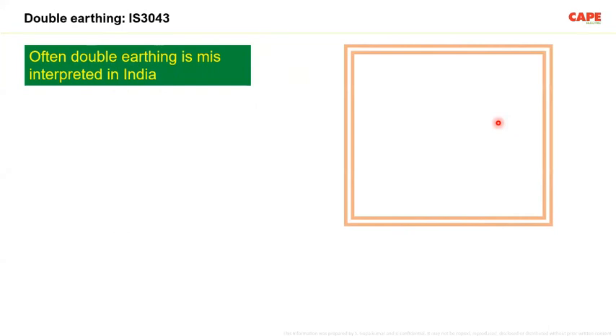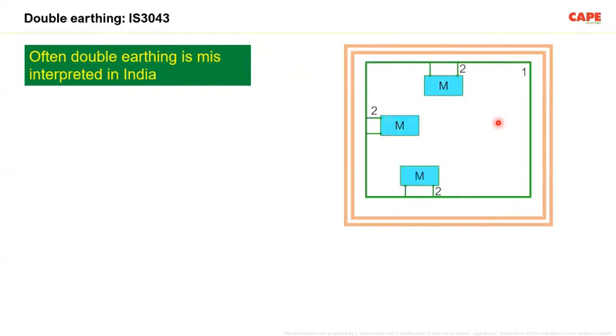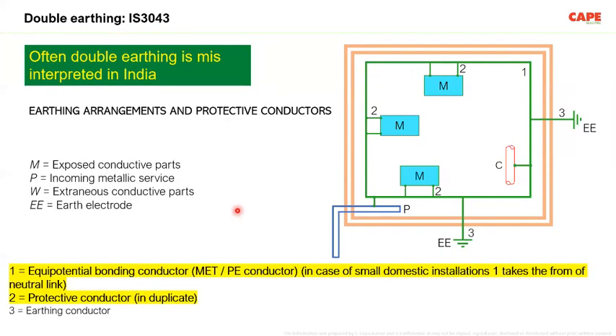You can find this picture in IS 3043, I think picture number 14 or 15. I don't remember the number exactly. In the IS standard it's a black and white picture; I put it in color. So you can see the building, and this green line which is running all around, item number 1, is the protective equipotential bonding. Number 1, the green ring, the equipotential bonding conductor. The old name is equipotential bonding conductor, but the new names are either an MET, main earthing terminal, or a protective earth conductor.